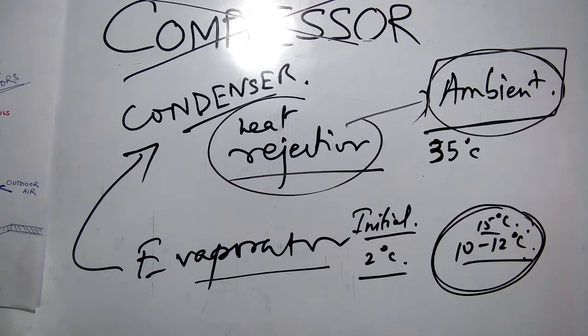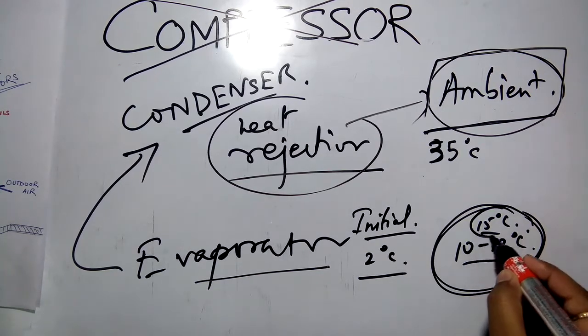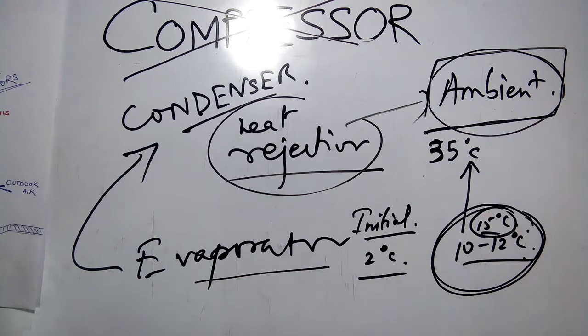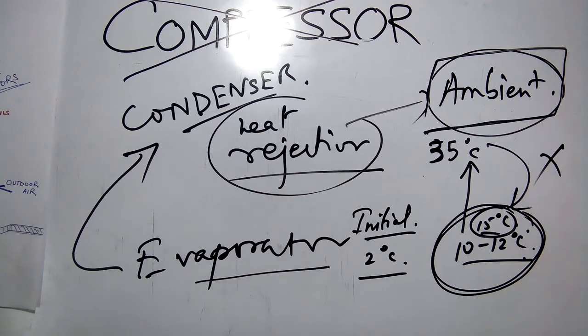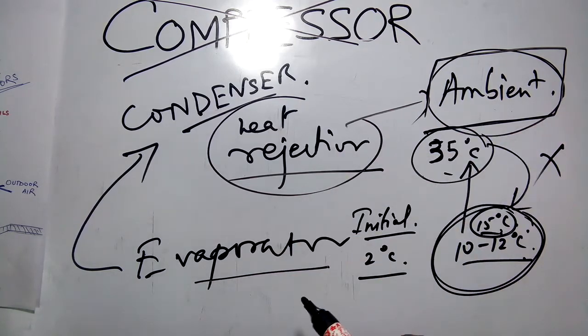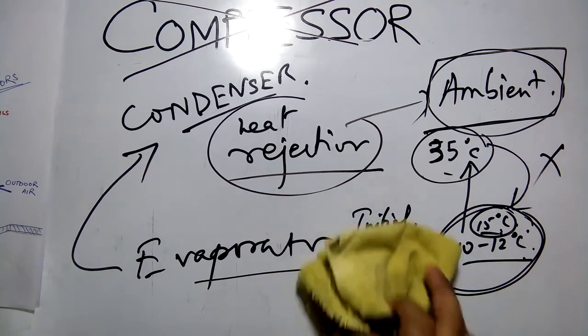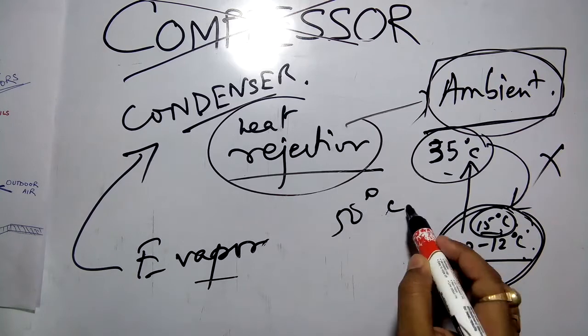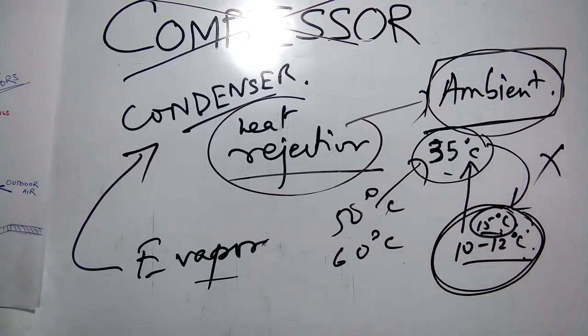Here is why the compressor is essential. When the refrigerant leaves the evaporator, its temperature is about 15°C (it has absorbed heat from the warm room air and vaporized). The ambient temperature outside in summer is about 35°C. For heat rejection to occur in the condenser, the refrigerant must be hotter than the ambient — heat cannot flow from a lower temperature to a higher temperature. If we send the 15°C refrigerant directly to the condenser, the ambient at 35°C would actually give heat to the refrigerant, which is the opposite of what we want.